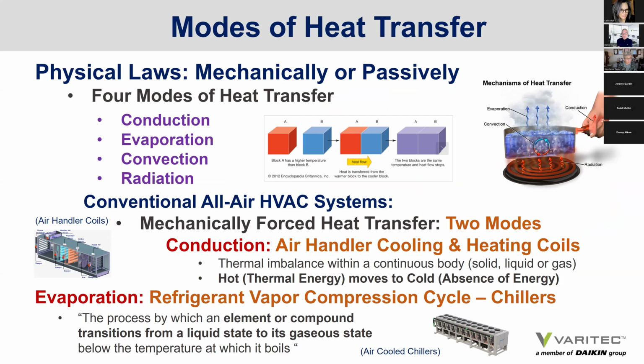Conventional all air or mixed air HVAC systems use mechanically forced heat transfer modes. Conduction, where air that is being conditioned is in direct contact with the fins of cooling or heating coils. And then evaporation, actually it's evaporation condensation that we see in vapor compression cycles in chillers, where heat transfer is controlled by pressure control within the vapor compression cycle. But it's an evaporation condensation of refrigerant that allows for that transfer of energy. We also see it in packaged DX equipment on roof. DX equipment uses the principle of evaporation and condensation in order to move energy from the building to outdoors.